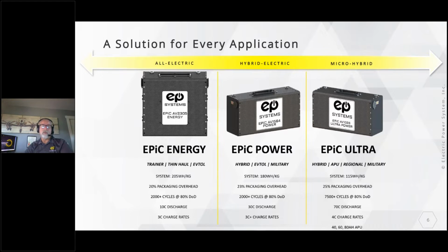You can see that the modules, although they have different shapes, are common in construction. As opposed to other battery systems, like automotive, where modules are put into a bigger case, these are designed to be used as-is, meaning the battery modules themselves are encased in a protective layer for containment of thermal runaway events. They're complete with the electronics inside to manage the cells, a liquid cooling mechanism, support and ventilation of a thermal runaway event, and communications to the battery management system for voltage management, state of charge estimation, and temperature measurement. All those features are integrated into the modules.